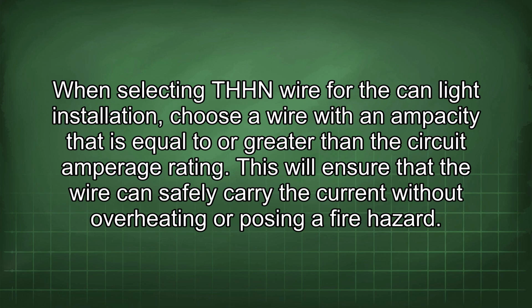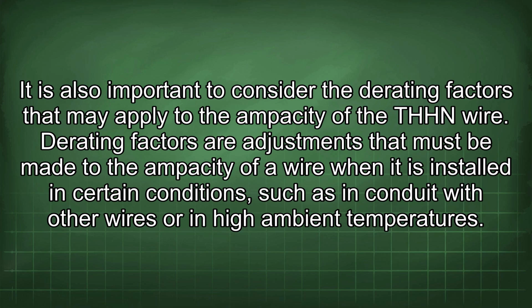When selecting THHN wire for the can light installation, choose a wire with an ampacity that is equal to or greater than the circuit amperage rating. This will ensure that the wire can safely carry the current without overheating or posing a fire hazard. It is also important to consider the derating factors that may apply to the ampacity of the THHN wire.